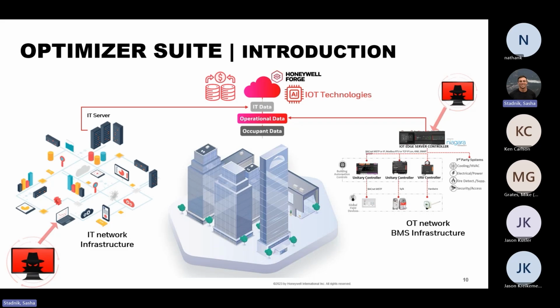This is the only controller in the Honeywell portfolio that you will find this port. This thing is completely physically isolated IP port. And you will tell me, so the information doesn't flow from one to the other? No, it does, but how it does it, it has an internal chip that is copying and pasting information from one side to the other. When this controller detects any vulnerability in cybersecurity, it locks completely. Once it's locked, there's no way you can go in and out.